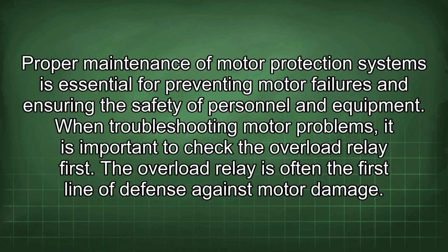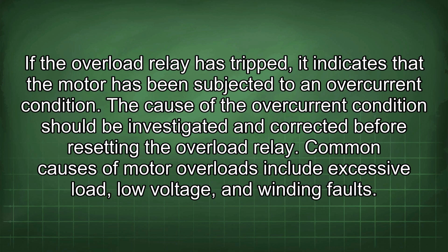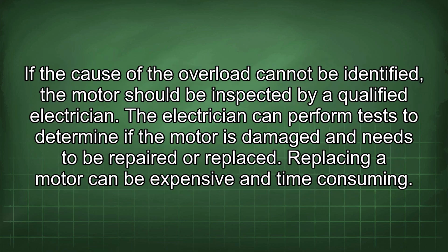When troubleshooting motor problems, it is important to check the overload relay first. The overload relay is often the first line of defense against motor damage. If the overload relay has tripped, it indicates that the motor has been subjected to an overcurrent condition. The cause of the overcurrent condition should be investigated and corrected before resetting the overload relay. Common causes of motor overloads include excessive load, low voltage, and winding faults. If the cause of the overload cannot be identified, the motor should be inspected by a qualified electrician. The electrician can perform tests to determine if the motor is damaged and needs to be repaired or replaced.